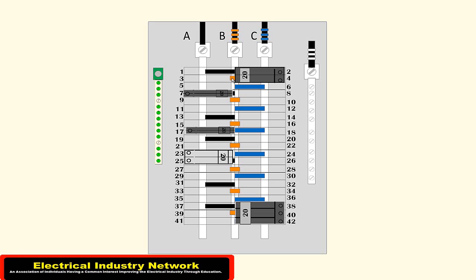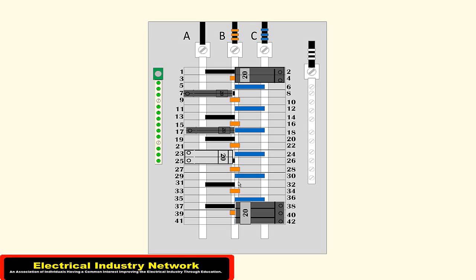So if you run it off of the B or the C and the A phase, you're fine. But what happens is you lose all these spaces for single-pole breakers, and that's what brings this all about.